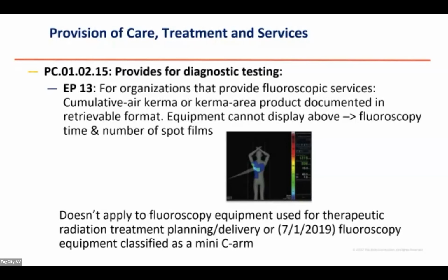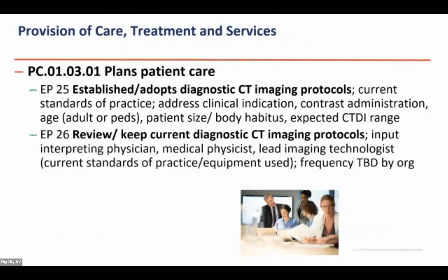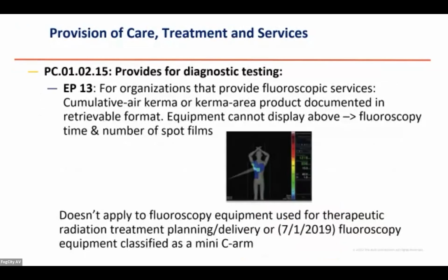Well, here's the story. Look at what you're billing for. To me, that's a nice rule of thumb. If on that unit you're billing for diagnostic procedures, then you know that you're using it as a diagnostic imaging device. And it's subject then to the performance evaluation for CT, and if it's fluoro, for doing the monitoring of exposure. Next slide.